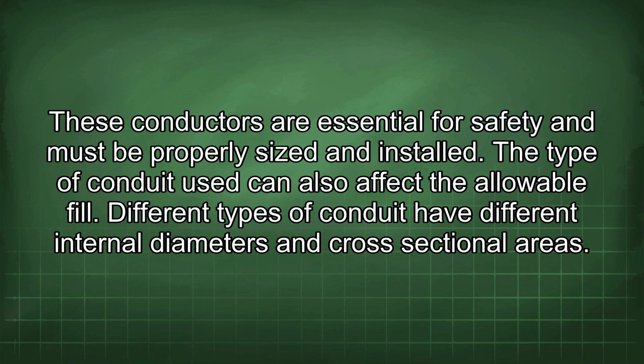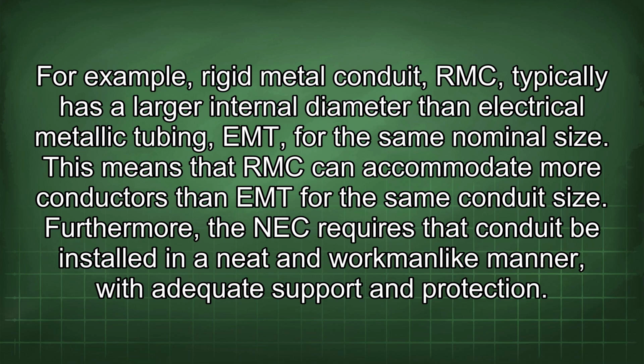The type of conduit used can also affect the allowable fill. Different types of conduit have different internal diameters and cross-sectional areas. For example, rigid metal conduit (RMC) typically has a larger internal diameter than electrical metallic tubing (EMT) for the same nominal size. This means that RMC can accommodate more conductors than EMT for the same conduit size.